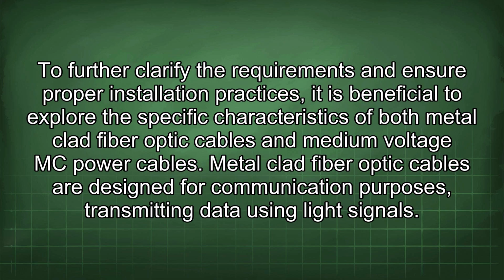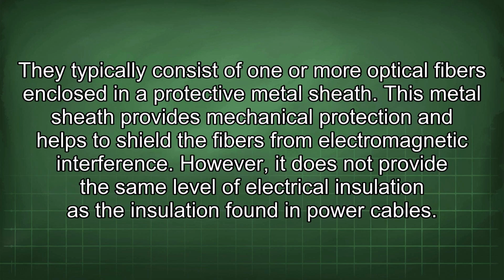To further clarify the requirements and ensure proper installation practices, it is beneficial to explore the specific characteristics of both metal-clad fiber optic cables and medium-voltage MC power cables. Metal-clad fiber optic cables are designed for communication purposes, transmitting data using light signals. They typically consist of one or more optical fibers enclosed in a protective metal sheath. This metal sheath provides mechanical protection and helps to shield the fibers from electromagnetic interference.